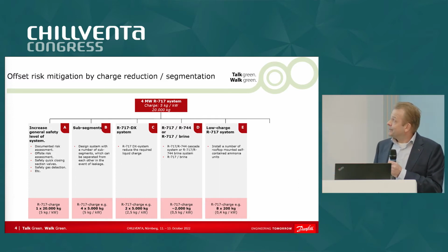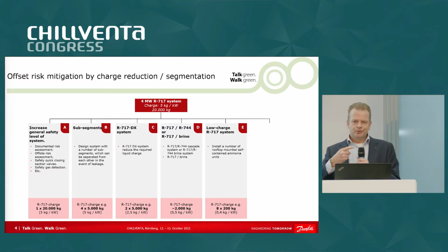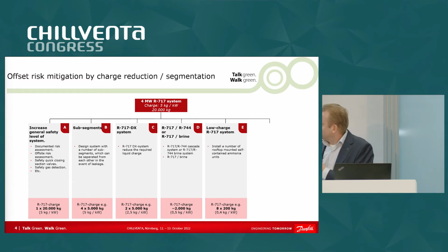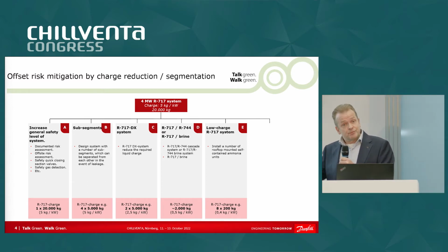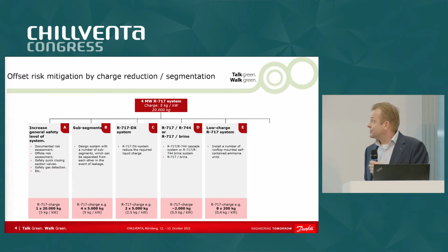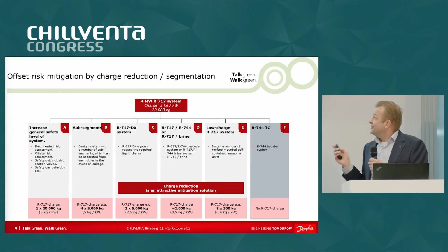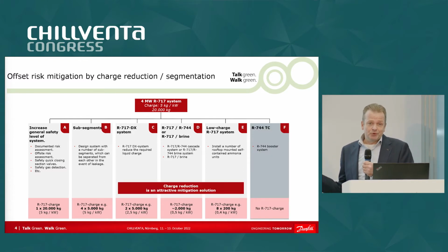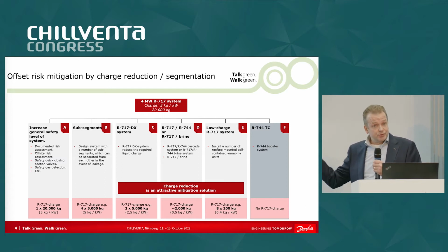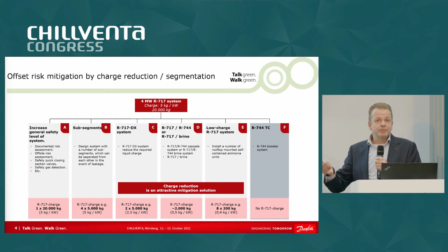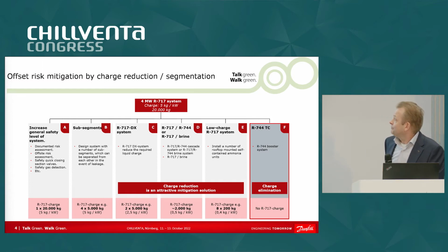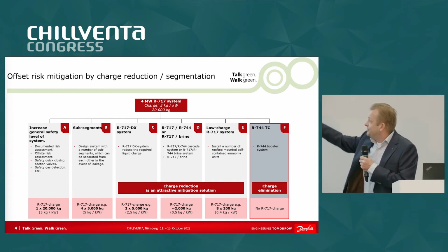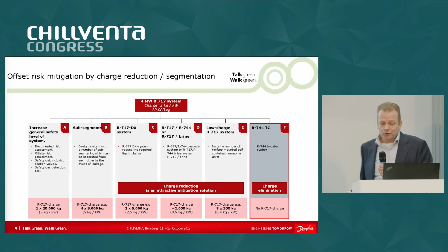The next one is separate low charge ammonia systems. Several self-contained ammonia systems on the roof, and the charge is really reduced even more. The last one is no ammonia anymore. And we see this more and more in bigger systems that CO2 transcritical takes over the smaller capacities, like 1, 2, 3 megawatt of the systems. So here we completely eliminate the charge, so there's no ammonia anymore.